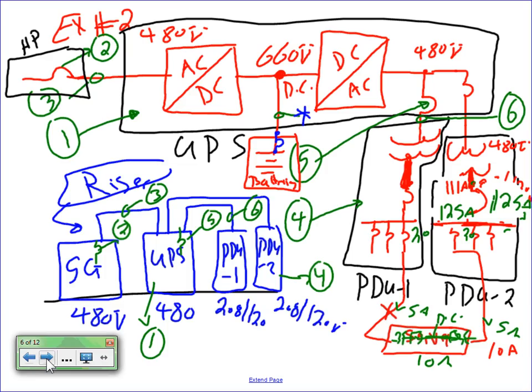We do not size the panel that is tied to the PDU. The PDU comes with a panel with a certain main and circuit breaker as well as the transformer, all in one big fat box. You size the input to the PDUs, but not the PDUs themselves, not the distribution panel. But I want you, William, to understand, when you size the PDU, you just size the transformer and the overcurrent protection on the transformer and the panel with an overcurrent protection device in it. The Revit PDUs that you have basically have the overcurrent protection device and the panel. It's just a panel. They don't have a transformer in them.